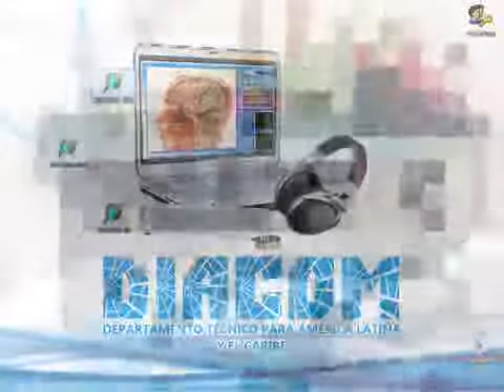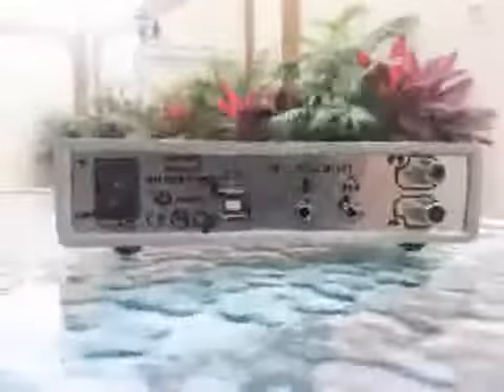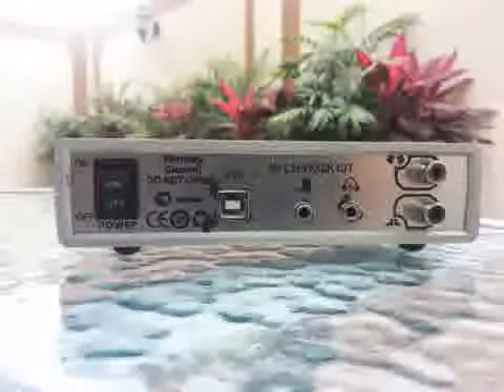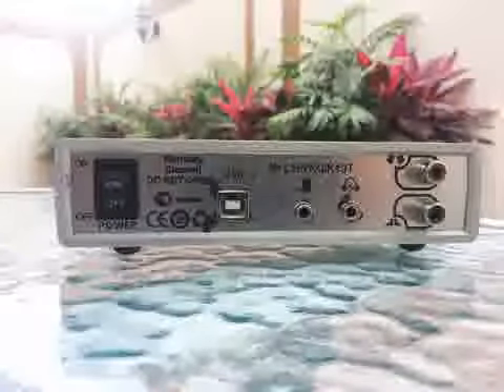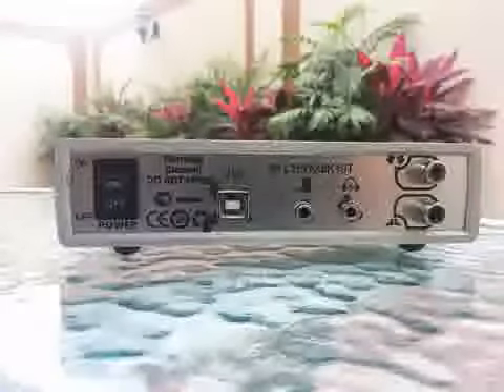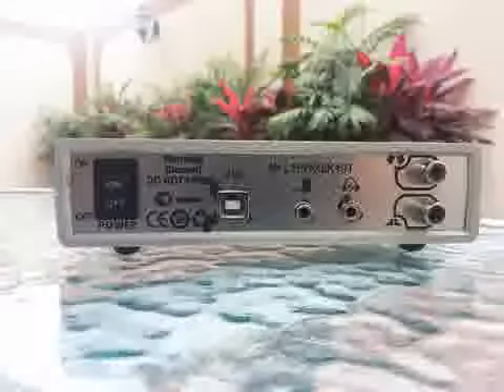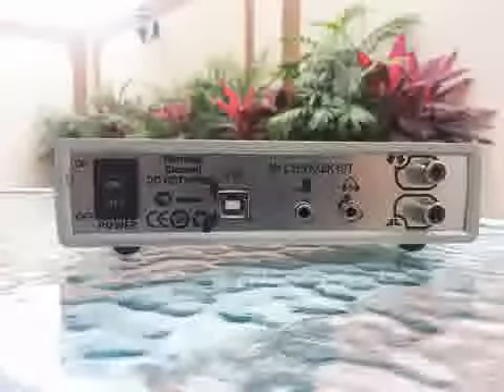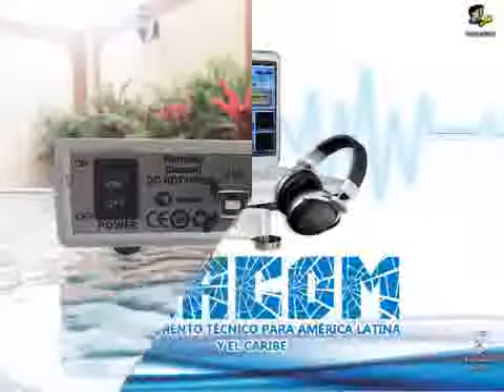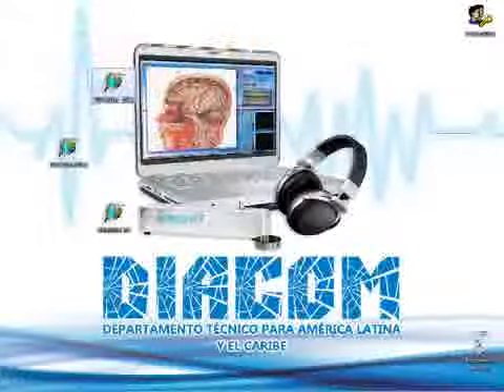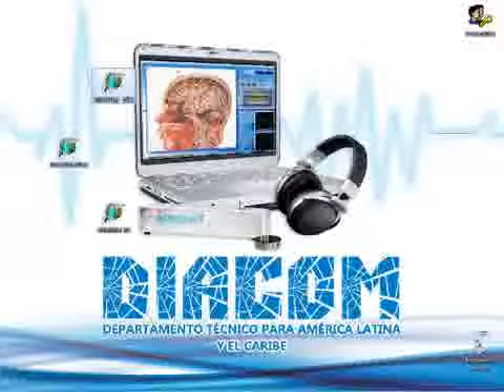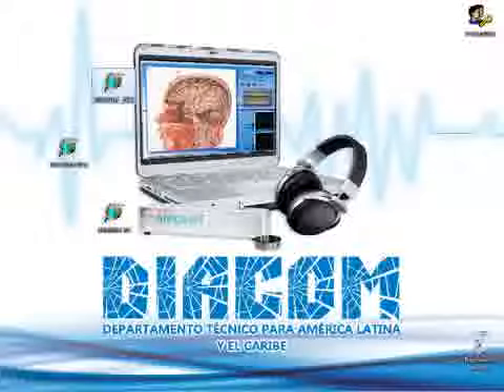It's worth remembering before starting that in the equipment's rear part you'll find the power button, which shall, obviously, be in on position before opening any program. Then there's also indicated in the plate the location of devices which shall be connected to equipment for correct performance of diagnosis or treatment. Those shall always be appropriately placed, be that the bioinductor, resonant base, or the FREC therapy cables.